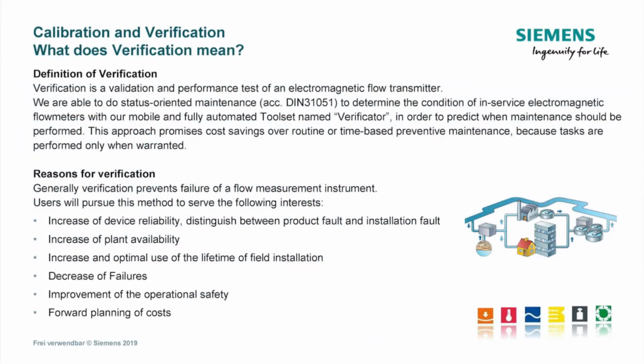What does verification mean? Verification is a validation and performance test of an electromagnetic flow transmitter. Siemens is able to do status-oriented maintenance, in accordance with DIN 31051, to determine the condition of in-service electromagnetic flow meters, with Siemens' mobile and fully automated toolset named Verificator, in order to predict when maintenance should be performed. This approach promises cost savings over routine or time-based preventive maintenance, because tasks are performed only when warranted.